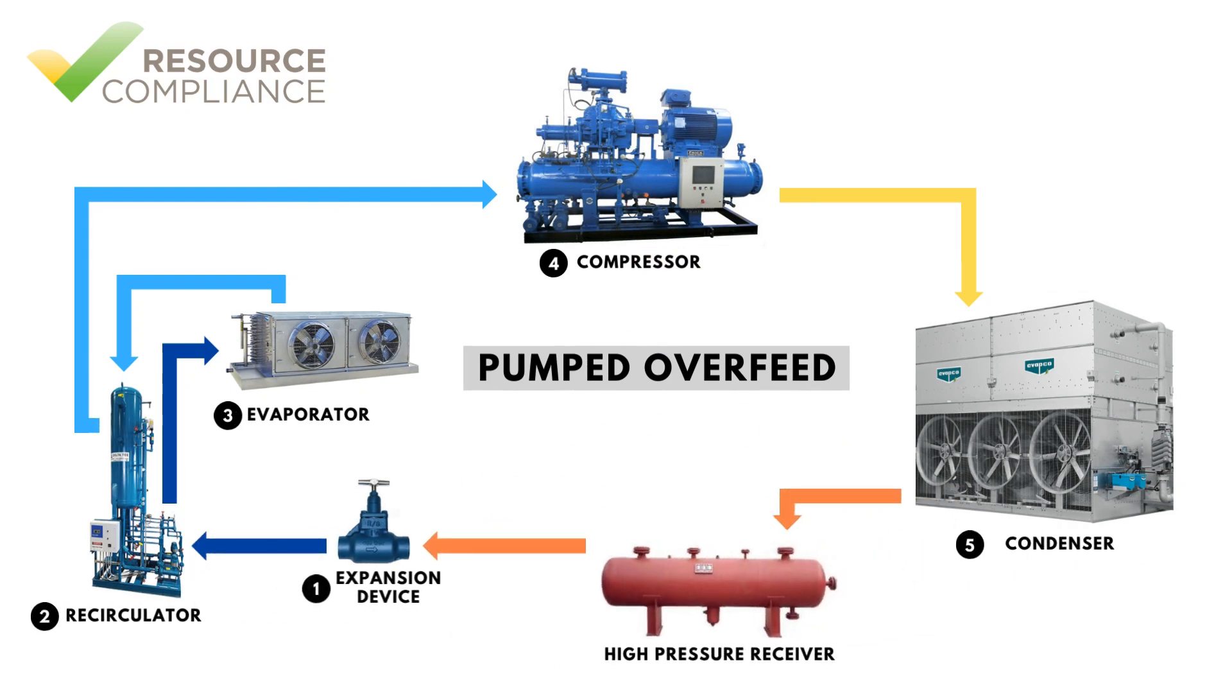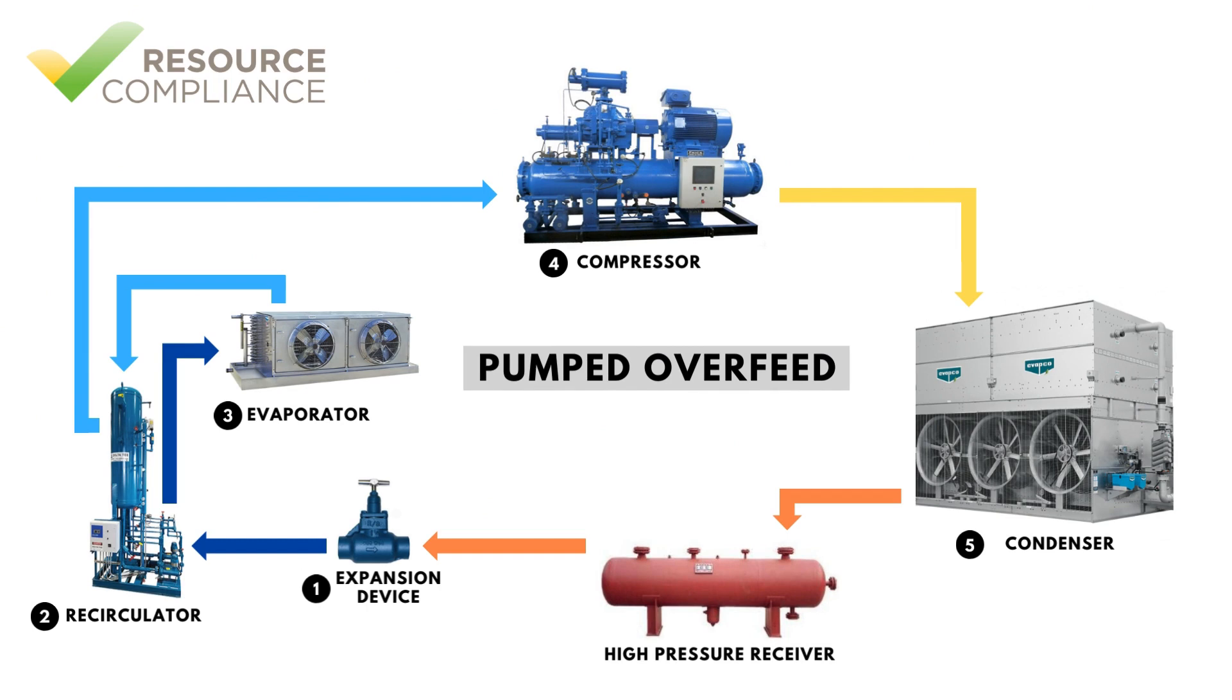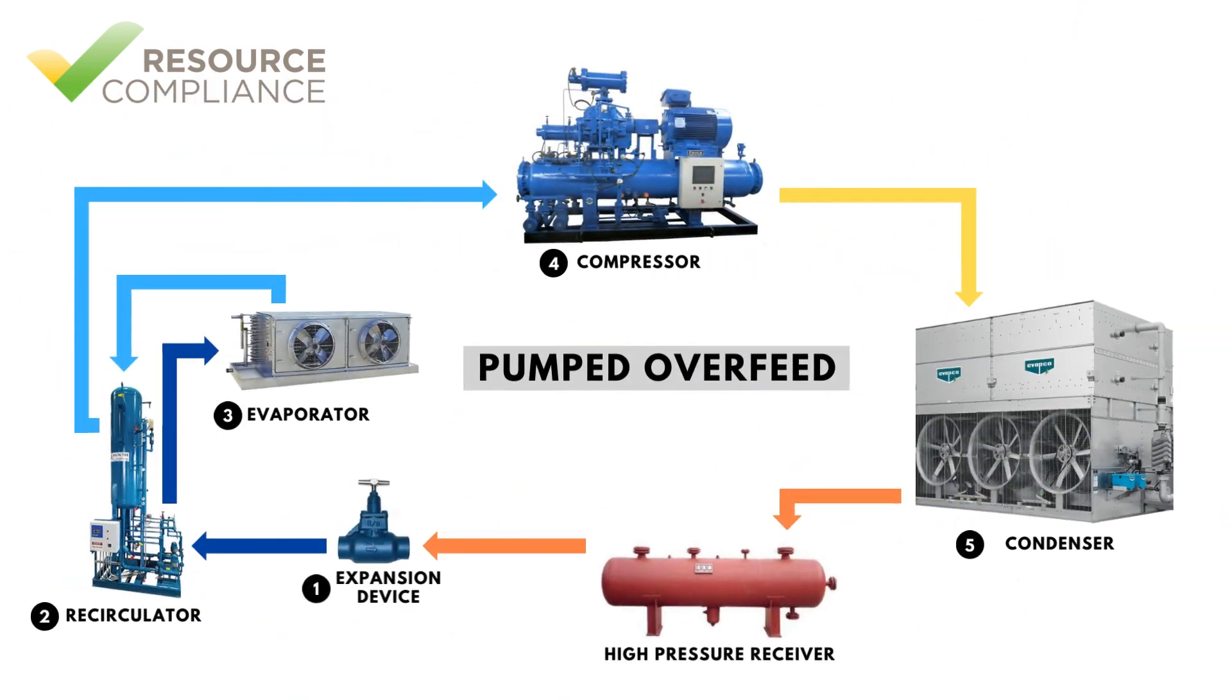A pumped overfeed or recirc system is similar to the gravity flooded system in that it utilizes a vessel that was not part of the DX system. In a pumped overfeed system, however, the vessel, often called a recirculator, is not located above the evaporator.